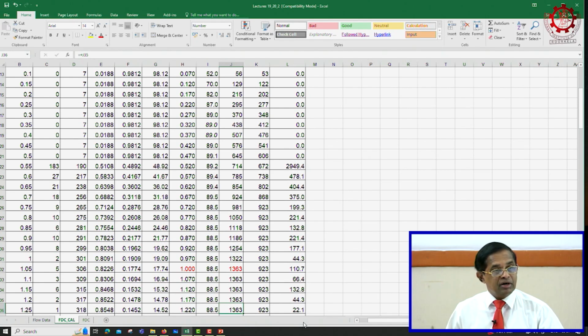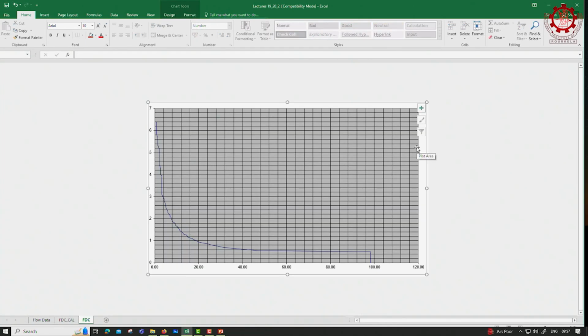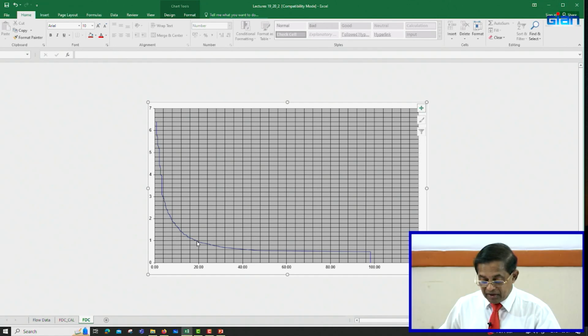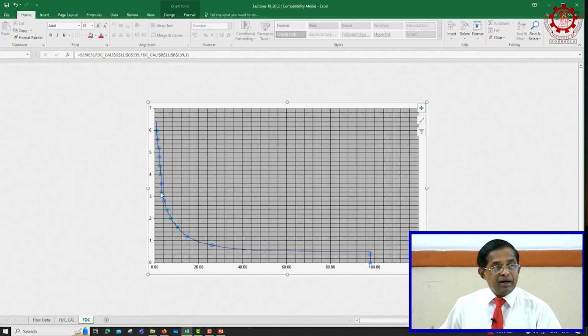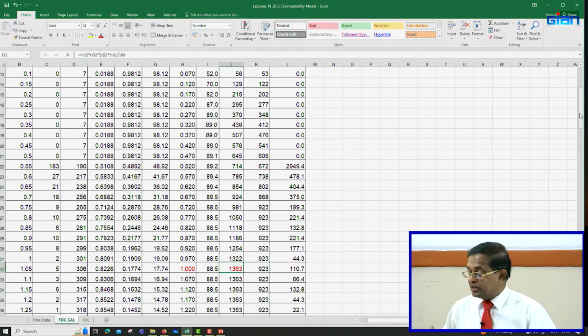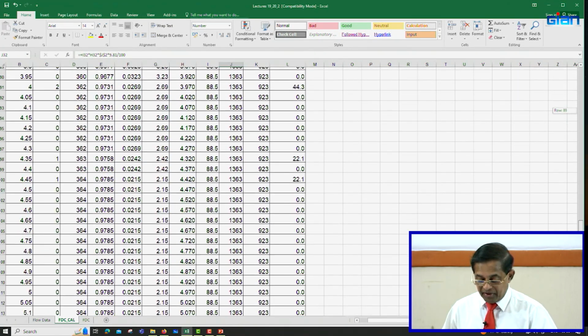Flow increases, but we cannot have more, because our plant is limited to 1 cubic meters per second flow rate. So, our rated flow is 1 cubic meters per second here, right. So, even though you have higher flows, your plant does not have the capacity to generate. You have limited the plant capacity corresponding to 1 cubic meters per second flow rate, right. That is why we freeze it here. So, at 1 cubic meters per second flow rate, plant capacity is 1363. Even though the flow is increasing, our plant capacity will still remain at 1363, because you cannot generate any more. Your plant does not have capacity. Your turbine and generator are all sized to this 1 cubic meters per second rated flow, right. I hope you understand. That is why I have frozen it beyond that, right.